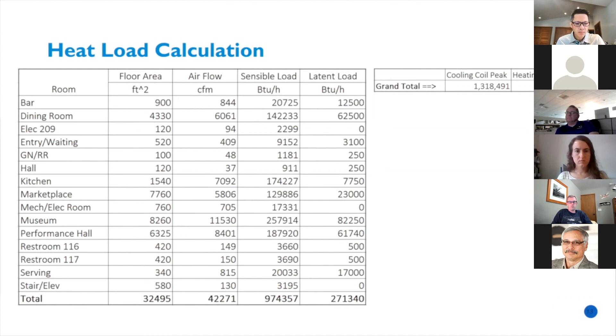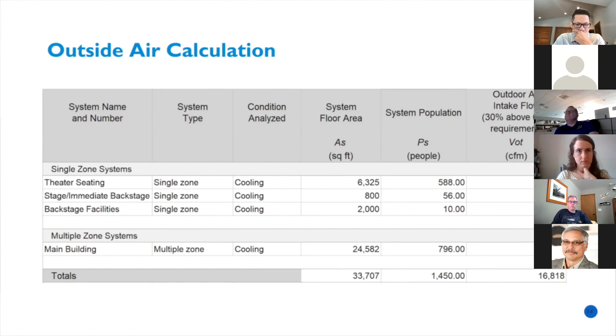Our outside air calculations tell us how much fresh air to introduce into the building depending on space usage and room size. So for example, in a zone such as our theater seating, we are going to have a higher outdoor air intake flow to compensate for the density of people. We also decided to size up our outside air to get extra LEED points. When selecting equipment, the theater system was designed separate from the main building according to acoustic demands. The seating is cooled separately from the stage, and extra air conditioning is provided for the backstage area. The broken up units help keep noise levels down.